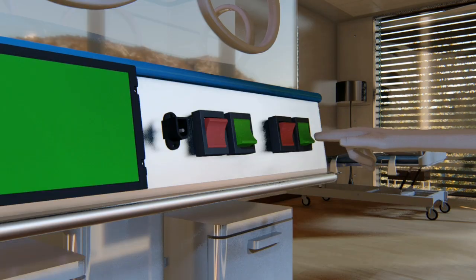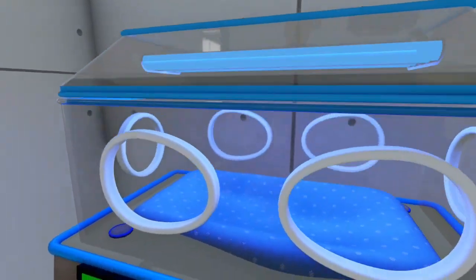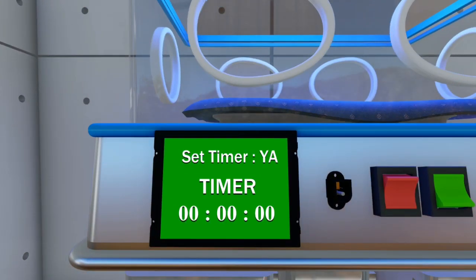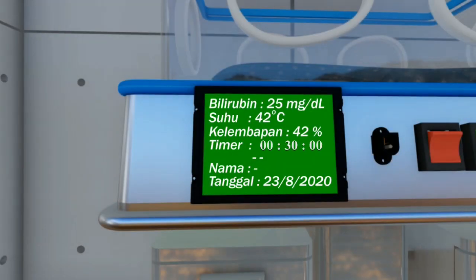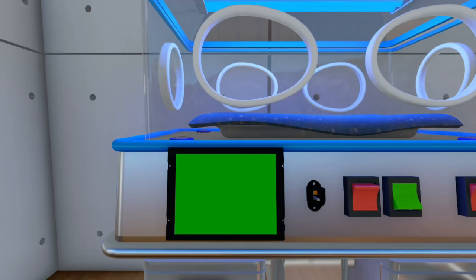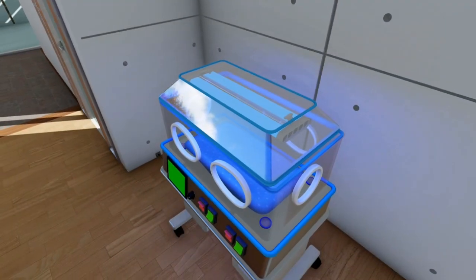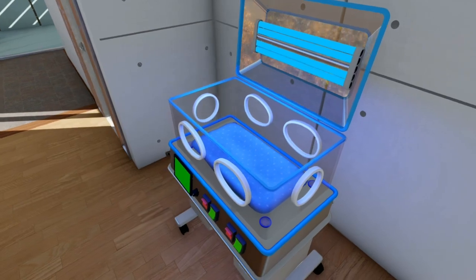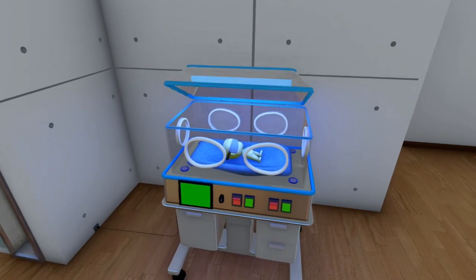For using phototherapy, press the green button to turn on the phototherapy system. When pressed, the blue light will automatically turn on. Then set the timer on the LCD screen and select yes, then set the time as needed. After setting the timer, the LCD screen will show bilirubin data, temperature, humidity, timer, name, and date. After confirming the system is working normally, open the incubator cover and place the baby, already wearing eye protection, as comfortably as possible on the incubator bed. Remember to close the incubator cover.